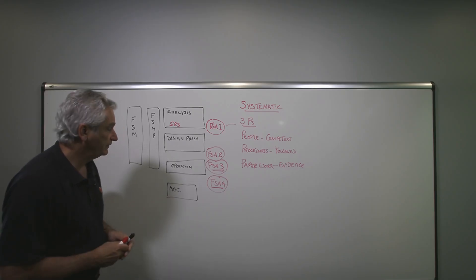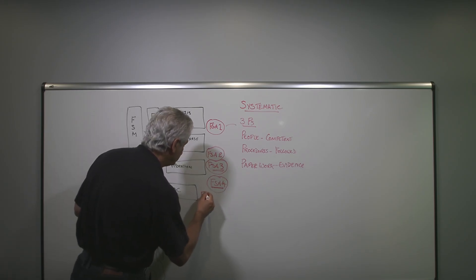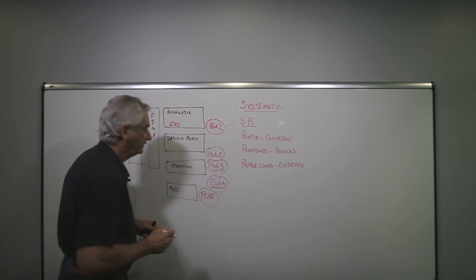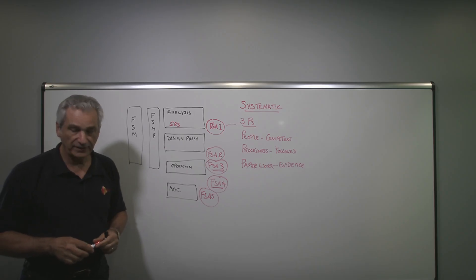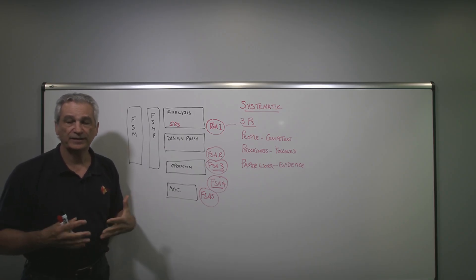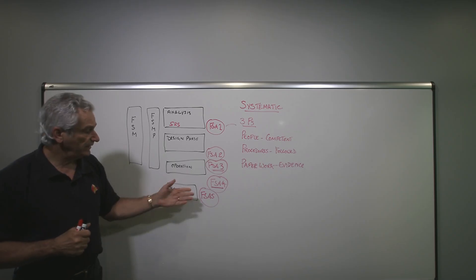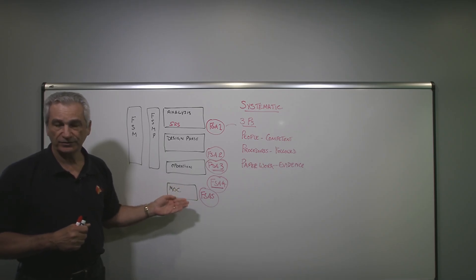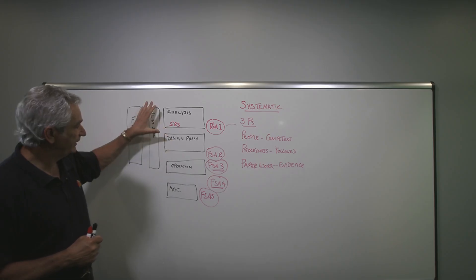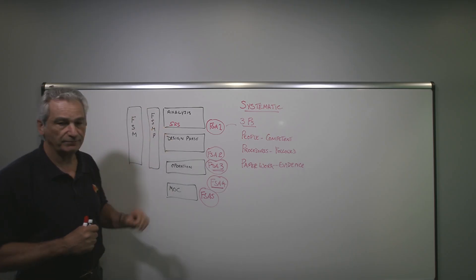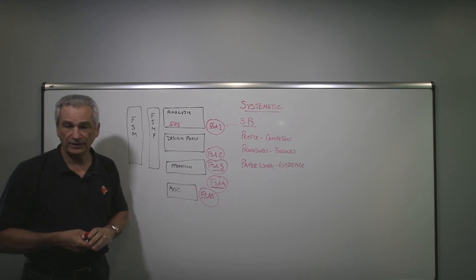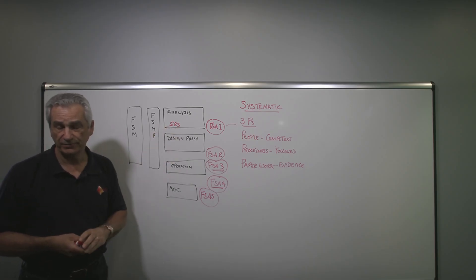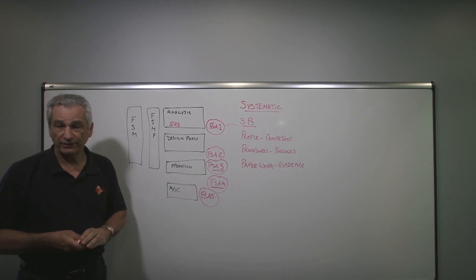The last functional safety assessment is the FSA-5. FSA-5 is if we determine that we need to make a change, we need to do a safety impact analysis on the change. And it has to be done by somebody who is independent and competent to do the work, to see, okay, what is the impact of this change on functional safety? And where do we have to go back to in the life cycle? And again, this would be part of our functional safety management and planning. We would go back to the relevant stage of the life cycle. We may end up having to make a change to the SRS, for example. So all of that is very important to follow.